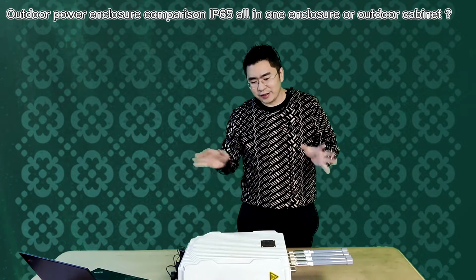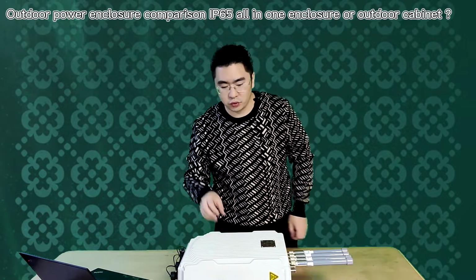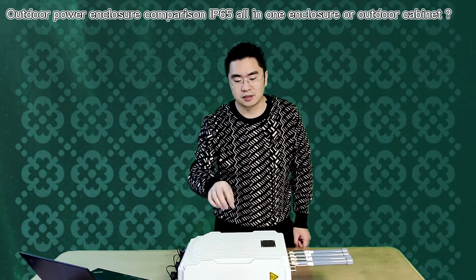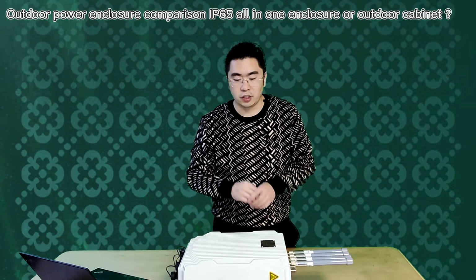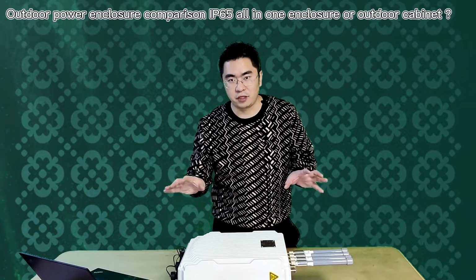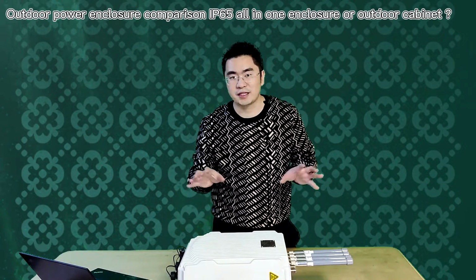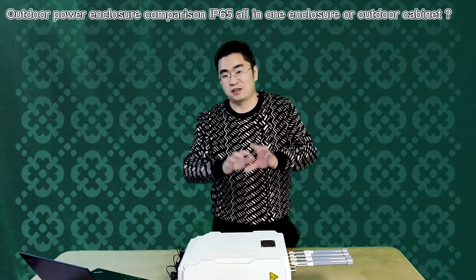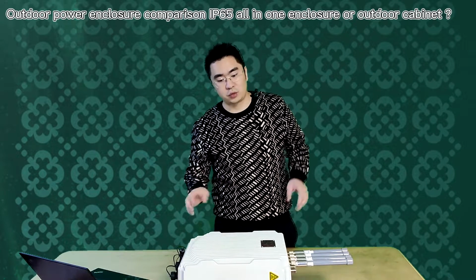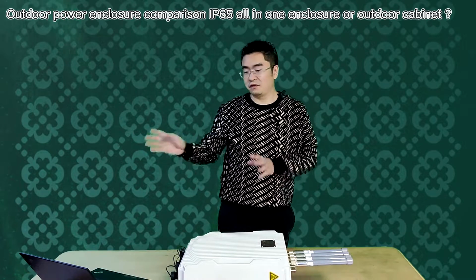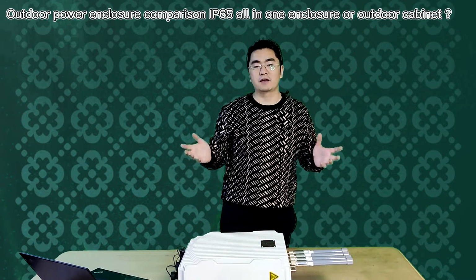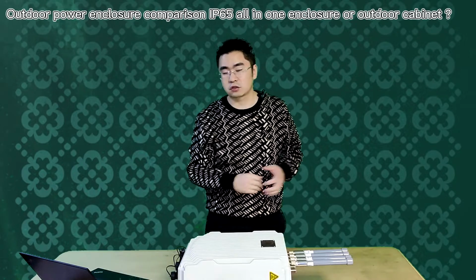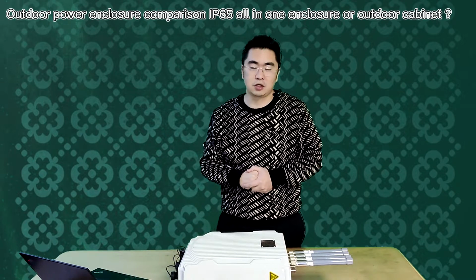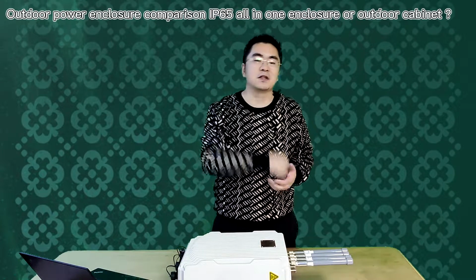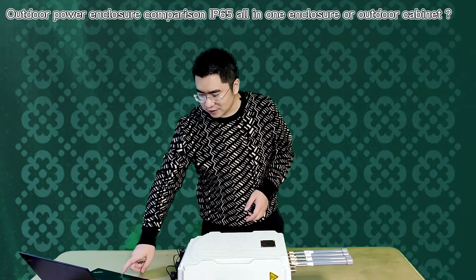But on the other hand, because of this kind of design, we put a battery management system inside the battery, so we can monitor the battery very well. Even if you have a massive quantity of sites, we know that 2 or 3 years, even 5 years later, which sites have a broken battery that we need to swap. We know clearly, so you don't have to do a site survey for every site, right? This is another difference.